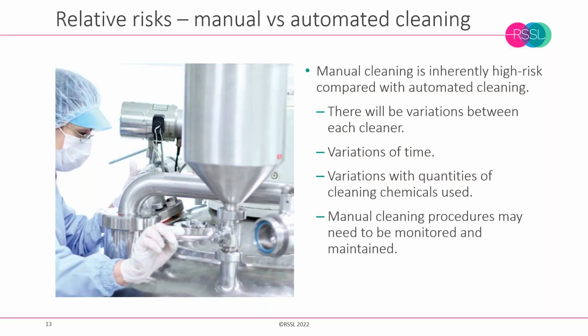So just looping back to manual cleaning. Now, cleaning is always preferably undertaken using automated systems because we can better factor in reproducibility and repeatability. But some items, due to their size or bulkiness, or because they can't be connected to clean in place technologies, will require manual cleaning, and that's generally through the activity of disassembling and then attempting to clean. So manual cleaning carries a considerably greater risk, and there's some debate you can see in literature about whether manual cleaning can ever really be validated at all, or whether it's more of a case of having sufficient controls to impart a level of assurance.